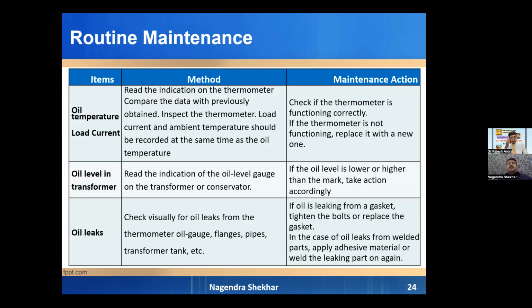So what is the routine maintenance of any transformer? Routine maintenance means what we do daily, hourly, weekly, and so on. First of all, on an hourly basis, we have to read the thermometer or temperature meter of the transformer at different loads, full load and off load. But for distribution organizations, it is not possible. This is possible only where our staff is deputed, like in substations. But we have to ensure that these thermometers or temperature meters are working properly. For distribution companies where unattended substations exist, we have to check it once in a while or every 6 months. Whereas for attended substations, we have to check it on an hourly basis.